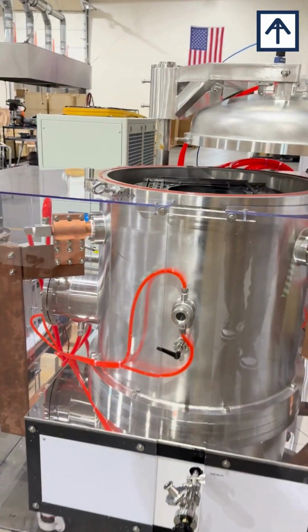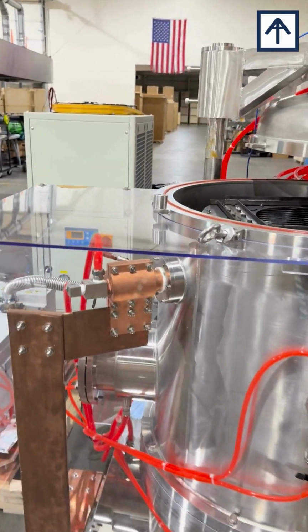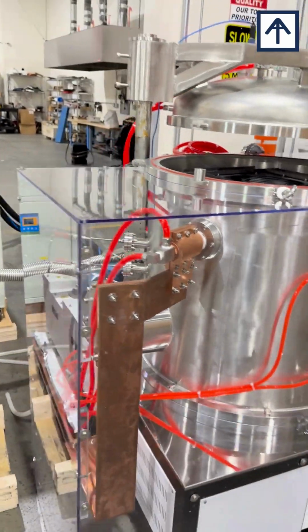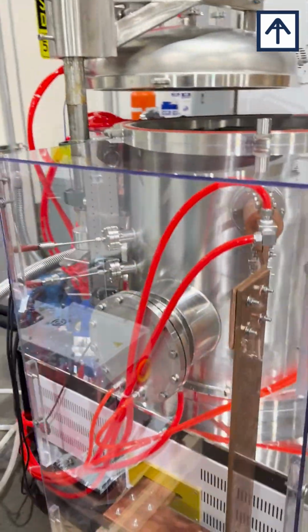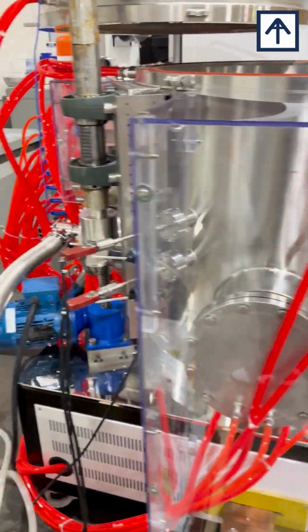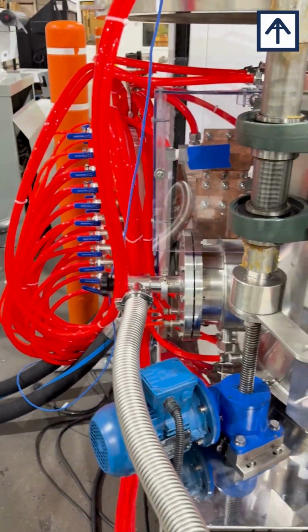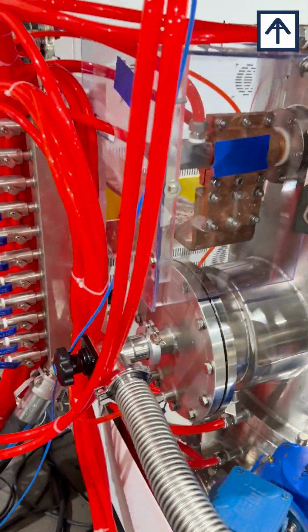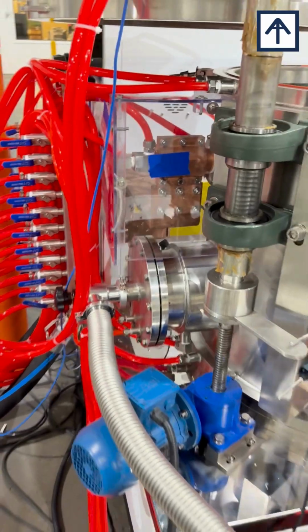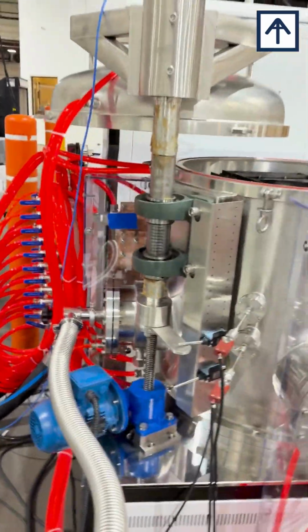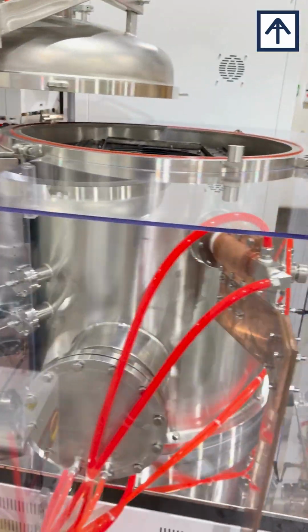Customizable vacuum systems. As I mentioned, the units are rated to be used with a turbomolecular pump, which is already designed with a flange assembly on the unit. So it can be used either on this port or the one on the back, where you can have the assembly directly connected to the turbo pump itself. You can also use it with a roughing pump or a diffusion pump to match your application needs.